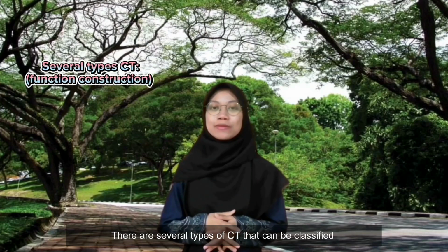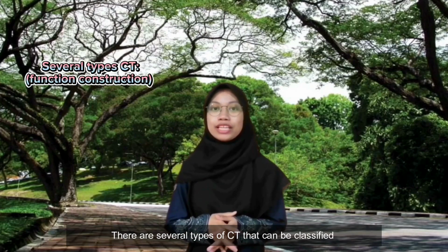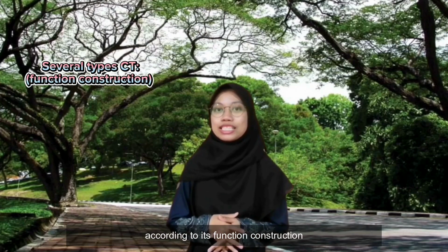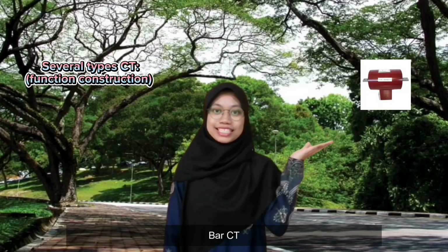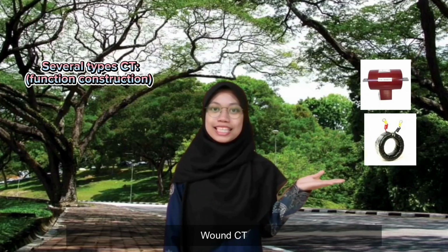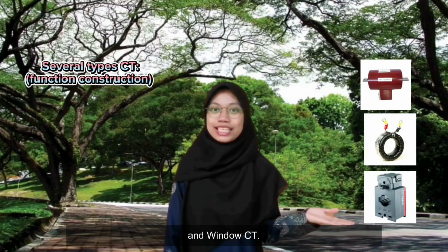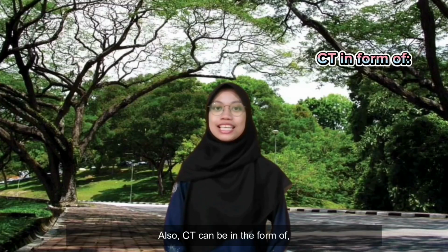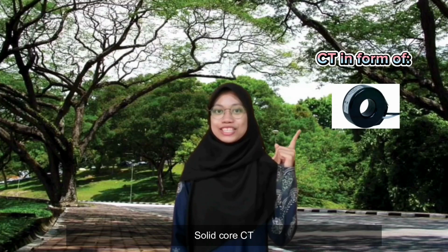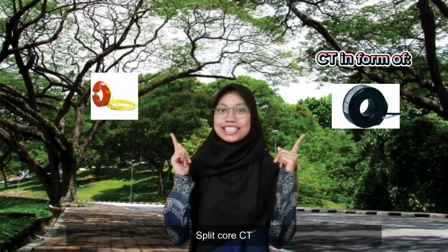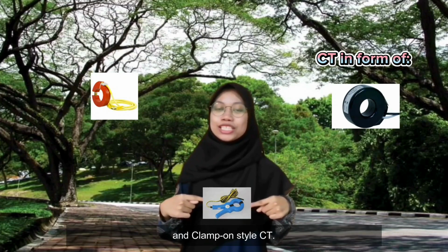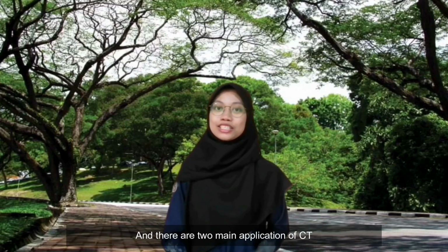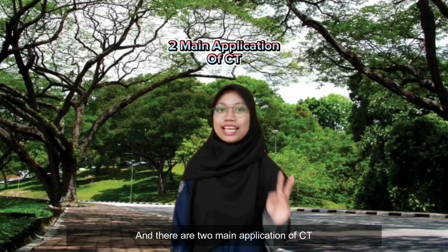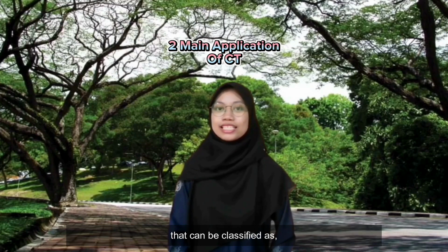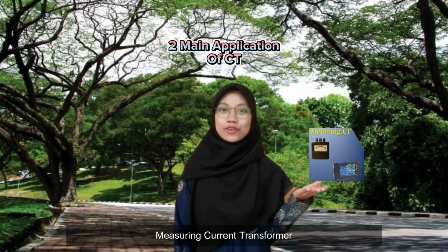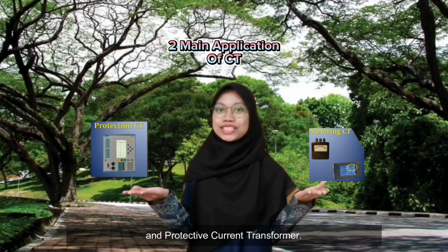There are several types of CT that can be classified according to their function and construction, which are bar CT, wound CT, and window CT. Also, CT can be in the form of solid core CT, split core CT, and clamp-on style CT. And there are two main applications of CT that can be classified as measuring current transformer and protective current transformer.